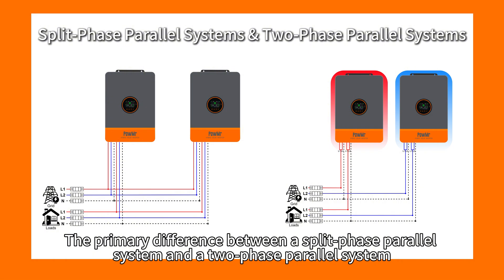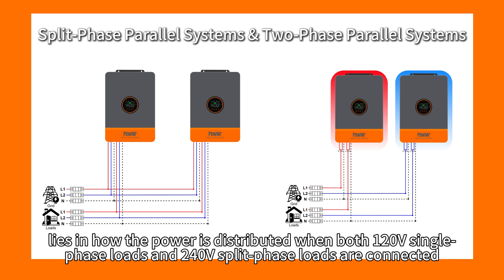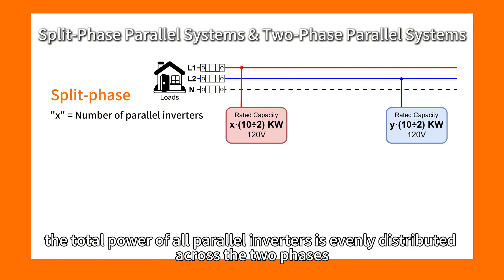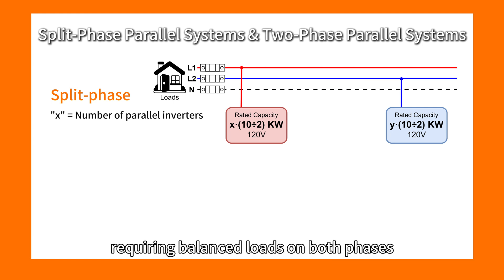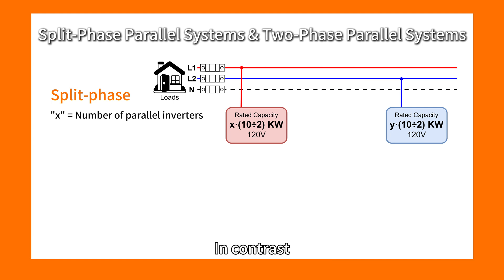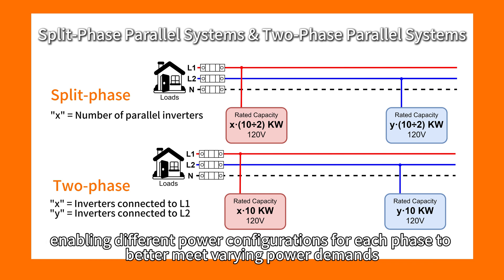The primary difference between a split-phase parallel system and a two-phase parallel system lies in how power is distributed when both 120V single-phase loads and 240V split-phase loads are connected. In a split-phase parallel system, the total power of all parallel inverters is evenly distributed across two phases, requiring balanced loads on both phases. In contrast, a two-phase parallel system allows flexible adjustment of the number of inverters connected to each phase, enabling different power configurations to better meet varying power demands.